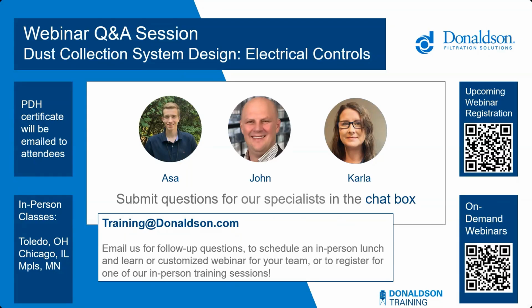All right, let me see. Next question. So for fans with VFDs, you use bag static pressure as your feedback and not an actual measure of airflow. I'll take this. The static pressure is typically measured in the dirty air plenum on one side, and then open to atmosphere on the other side. Folks at Donaldson and Control Assemblies came up with this quite a while ago as a way to not have to add extra devices into the system, because we can control the speed based on the static air pressure and try to maintain a very tight window of that static air pressure without having to add other devices to capture the velocity and do some other calculations.